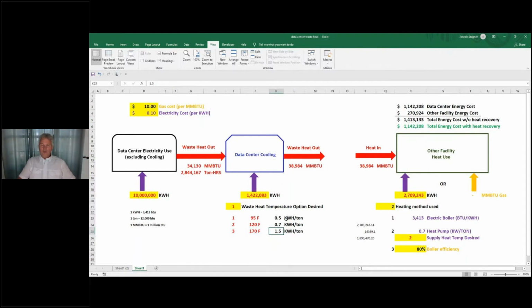So if we're just doing regular cooling of the data center and throwing the heat away through a cooling tower, then we're going to use option 1, 95 degrees, and it's going to cost us about 1.4 million kilowatt hours to run our chillers to extract the waste heat from the data center and exhaust it out a cooling tower. Meanwhile, what's the value of that waste heat? If I could somehow use that, does it have a value? I'm paying all the electricity in, I'm getting some work out of it. But what if I could get some more economic value out of it?